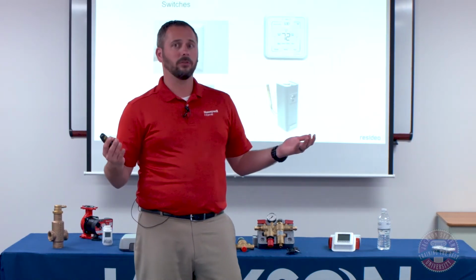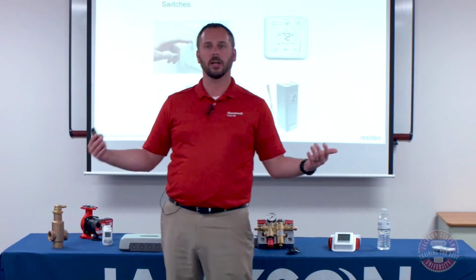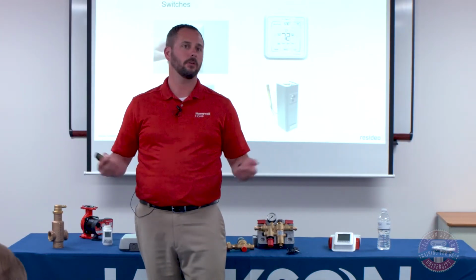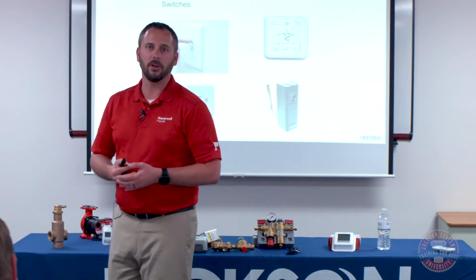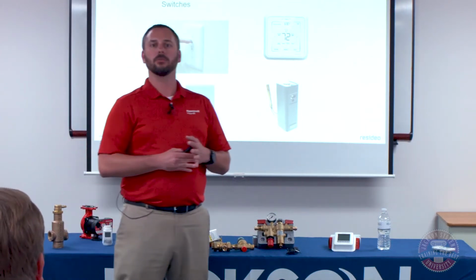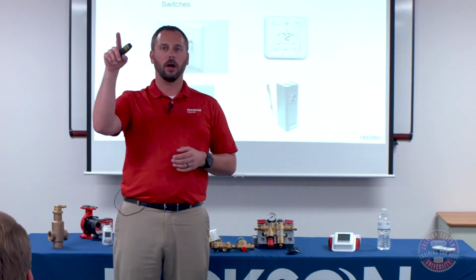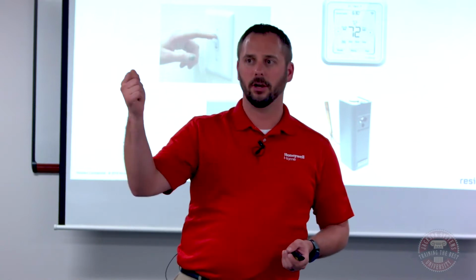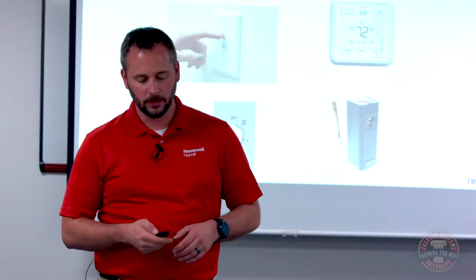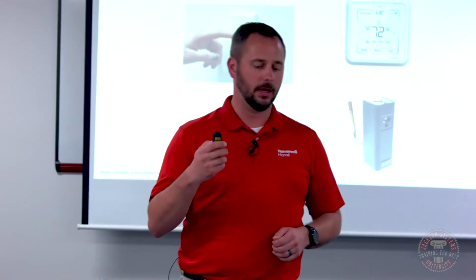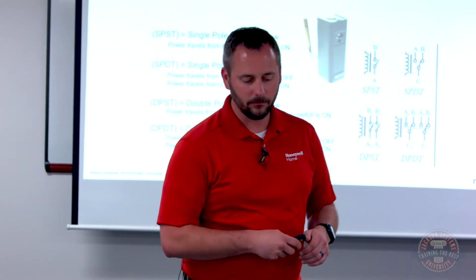Switches, a couple examples of switches. Probably the most common, based on the conversation we're having today, is thermostats. The thermostat you put up on the wall is nothing more than a very glorified switch. You're sending power up to it when there's a call for heat. In other words, when the temperature drops, you're going to send that power back out through it. It's no different than a glorified light switch. We also have Aqua stats, light switches literally, and then spa timers.